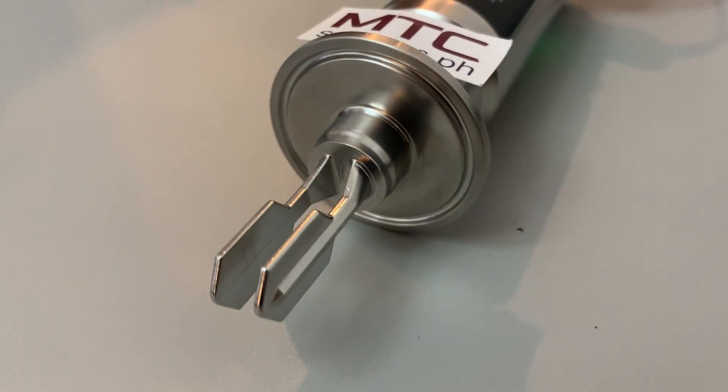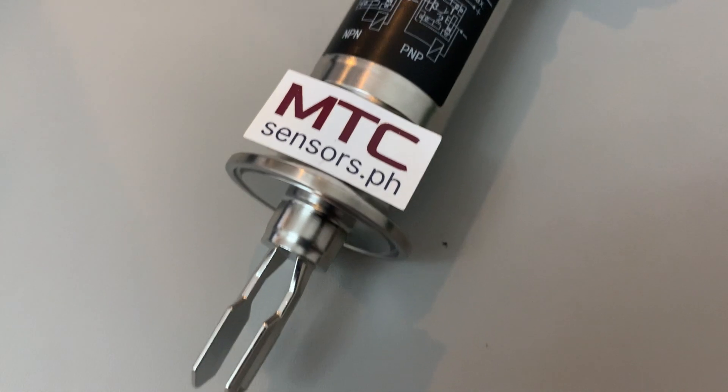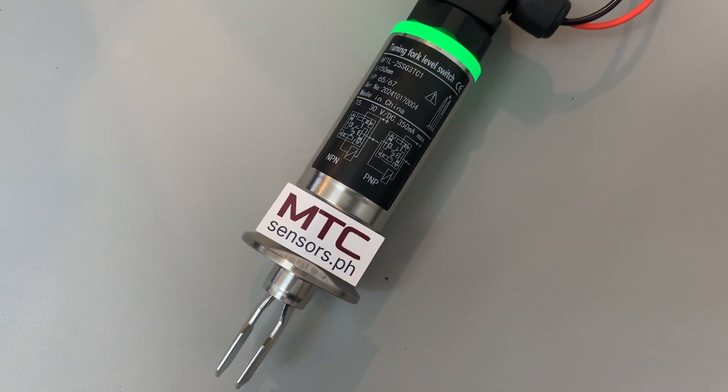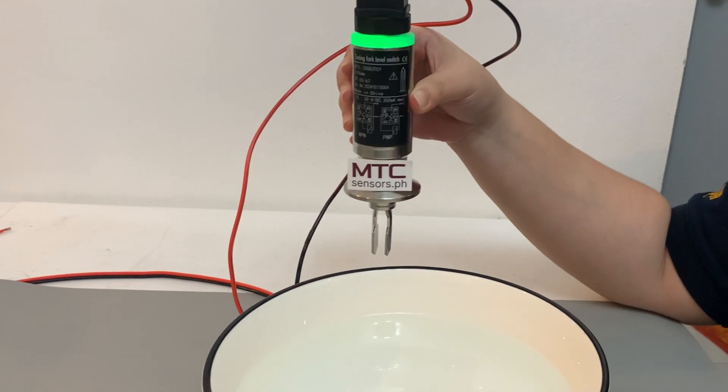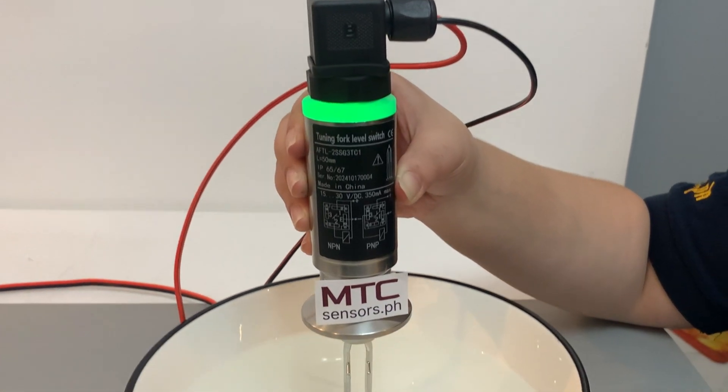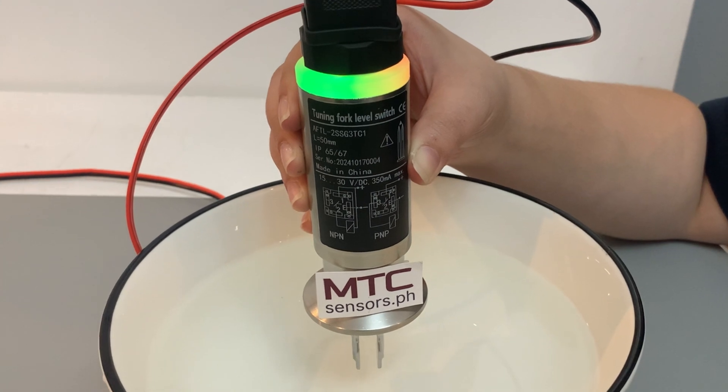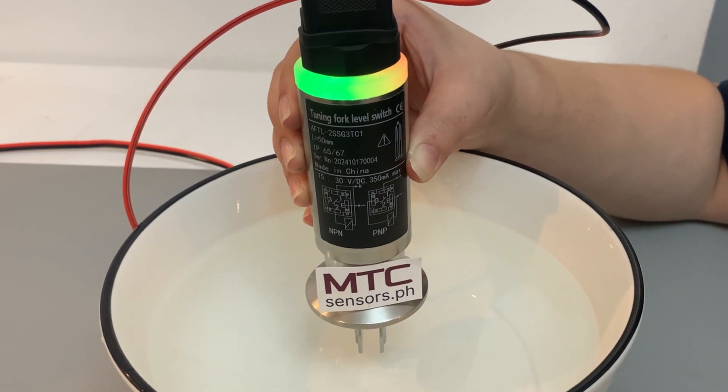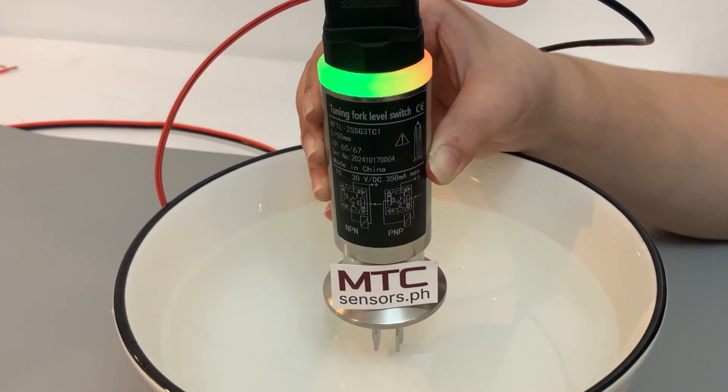The tuning fork-level switch operates based on the tuning fork principle. A piezoelectric crystal vibrates the tuning fork at a natural frequency of about 1,100 Hz. Changes in the liquid or solid level cause a shift in this frequency, which the electronics detect to switch output states.